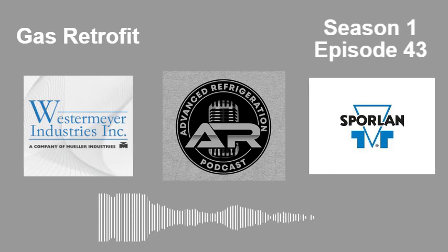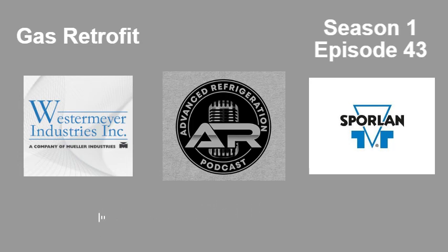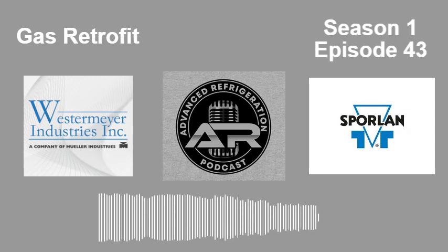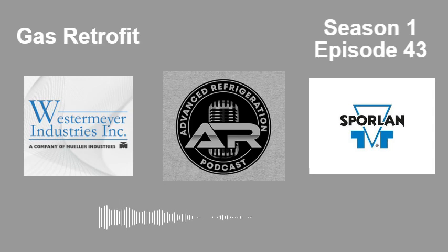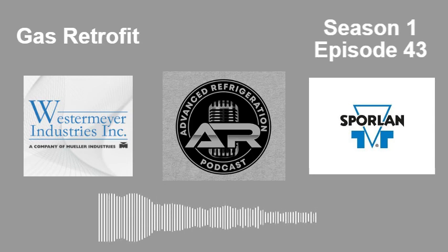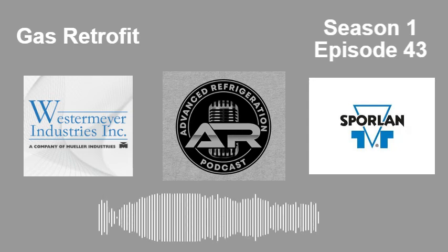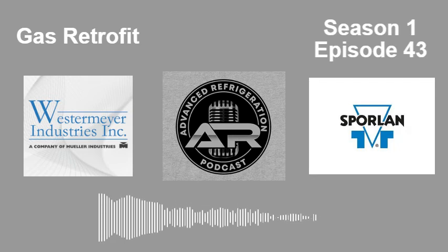You hear the tanks going off because they just hire the greatest people to do the recovery stuff. The last one, I think the guy blew off the reliefs off like 5 tanks. Damn. So, yeah, Golden Refrigerants, they're out of the Midwest. They showed up with 4 1,000-pound tanks on the last Costco I did, and 2 electric liquid pumps. He pulled 1,700 pounds of 22 in 38 minutes.